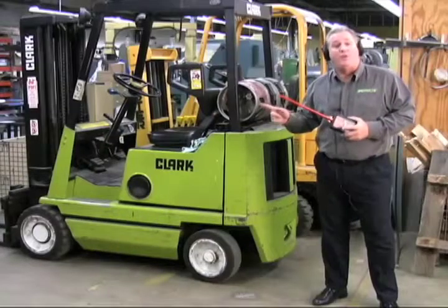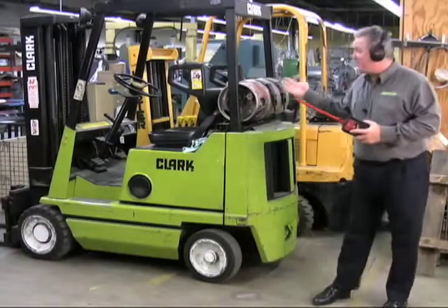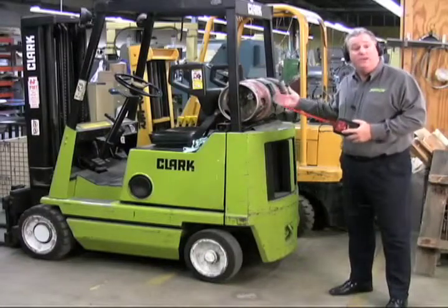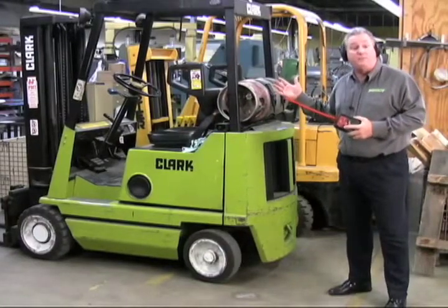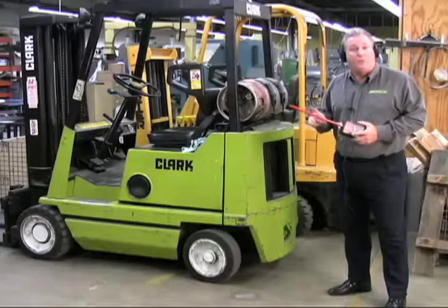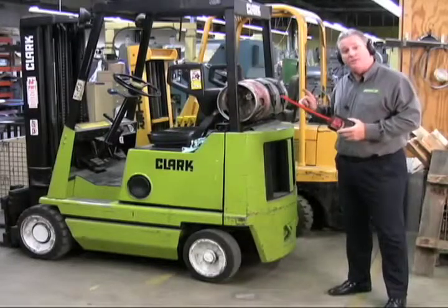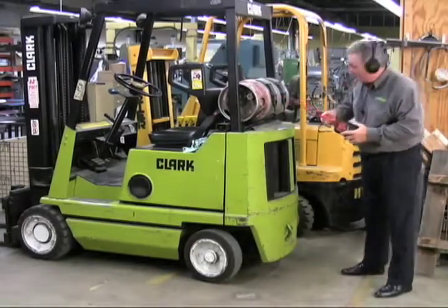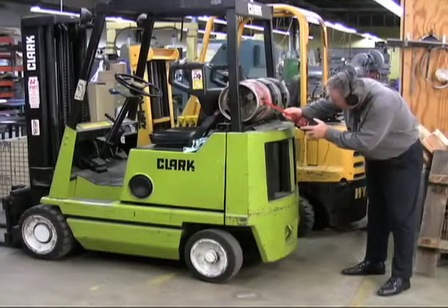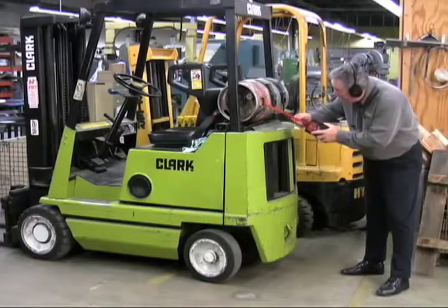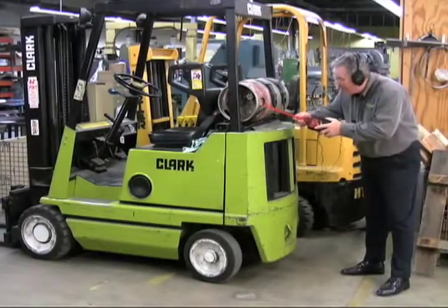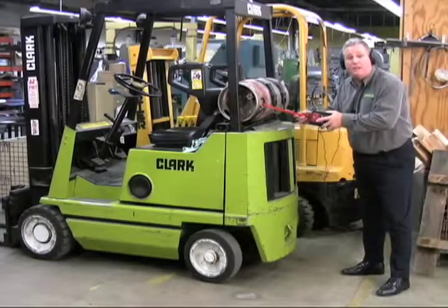Now we're going to test for propane gas leaks. Every facility uses one of these, a forklift. Propane gas is not only expensive, but it can also be very dangerous to the work environment if it's leaking. Here we're going to test for leaks on the propane gas tank. And once again, we found a leak right at the fitting.